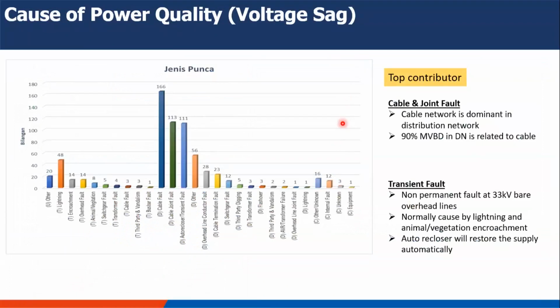So in TNB, what are the main causes of voltage sag? The top contributor will always be the cable, because we have so many underground cables and overhead cables connected. So the top contributor is cable fault, combined with excavation, joint failure and other cable failures. About 90% of breakdowns in the distribution network are related to cable, because there are so many cables in the distribution network.